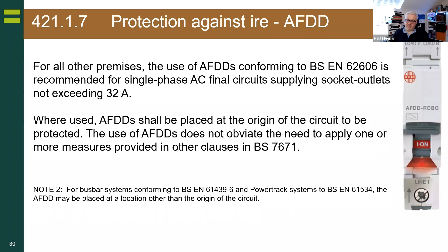Protect the installation better - where used, AFDDs placed at the origin. The use of AFDDs does not obviate the need to apply one or more protective measures. You don't just stick them in and not do bonding - it's additional protection.